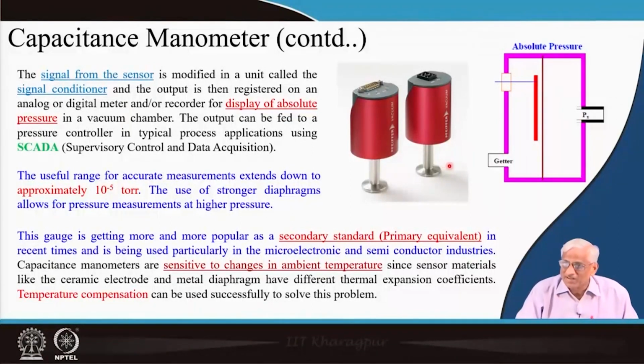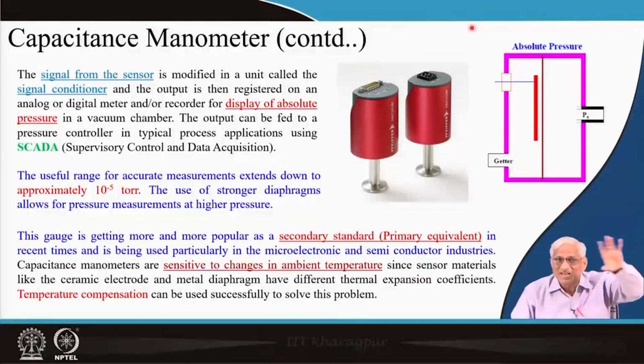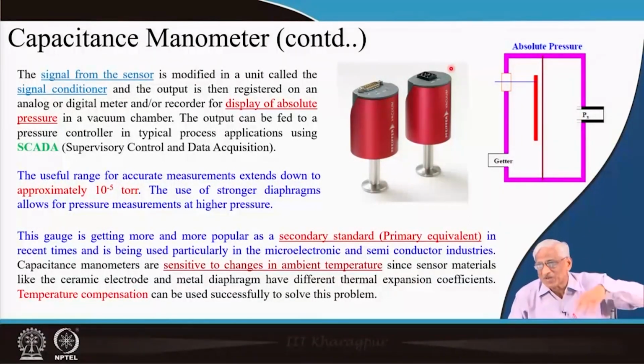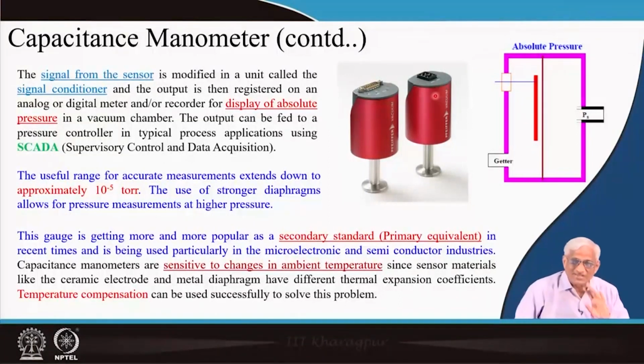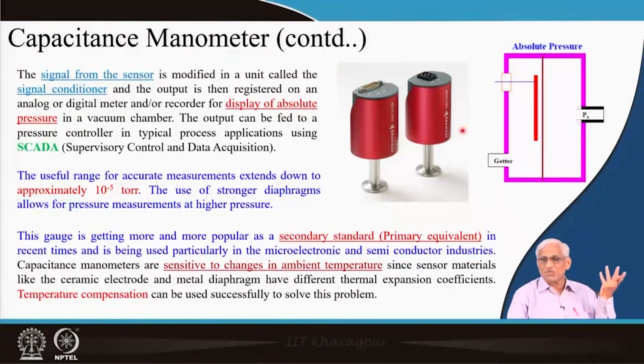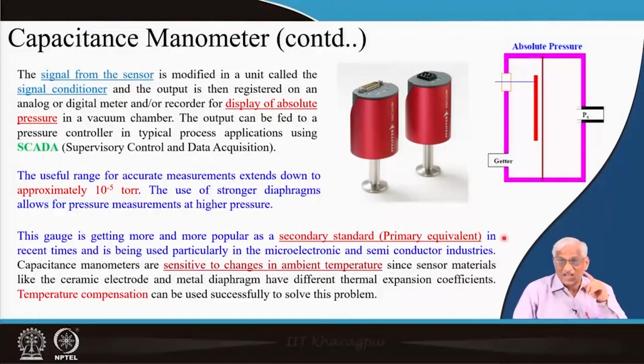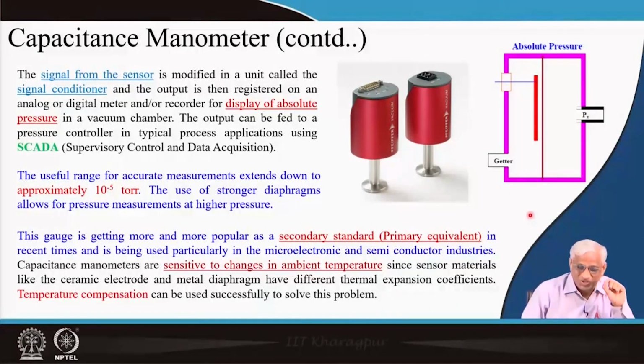Actually, we call it gauge, but in the real sense it is called a gauge head - that is the sensing element. The gauge is the place where you see the value displayed, but we normally call the whole thing a vacuum gauge. These have become habits over time, but scientifically you have to know the roots properly.